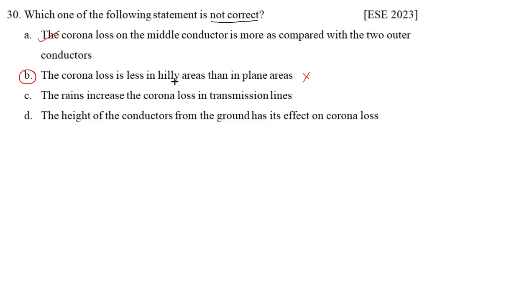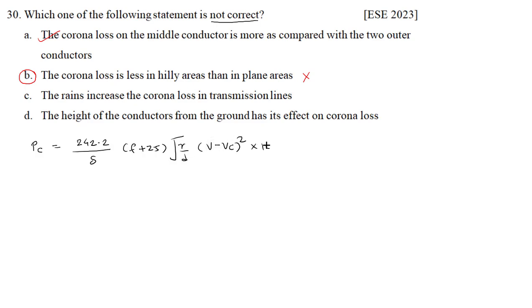Why is corona loss more in hilly areas? The expression for corona loss is: Ec = (242.2 / δ) × (f + 25) × √(r/d) × (V − Vc)² × 10⁻⁵ kW per km per phase. Here δ is the air density factor, f is supply frequency, r is conductor radius, d is conductor spacing, V is phase voltage, and Vc is the disruptive critical voltage. Corona loss is proportional to (V − Vc)².